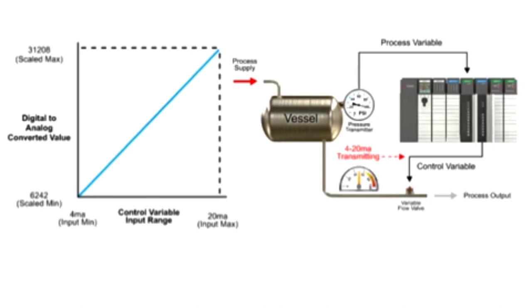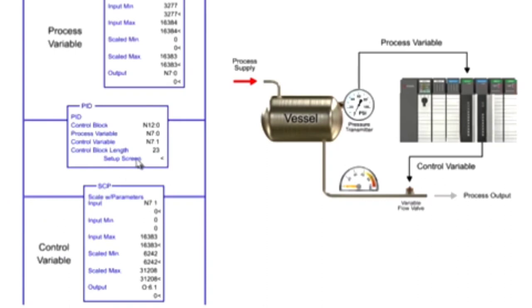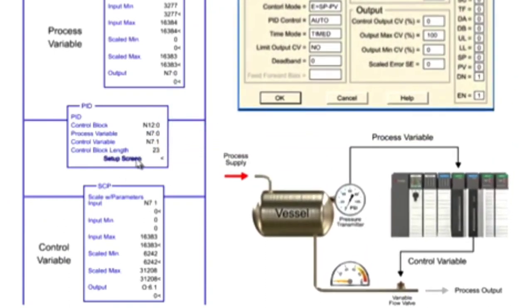The SCP output parameter is the file address of the analog output module. The analog output module converts the digital value in the range of 6,242 to 31,208 to an analog signal of 4 to 20 milliamps. The analog signal is then sent to the flow valve where the operating range is adjusted between 0 and 100%. With the data scaled using the SCP instruction, the process of controlling the pressure of the vessel to 50 PSI continues by entering the setpoint of 50 in the PID setup menu.